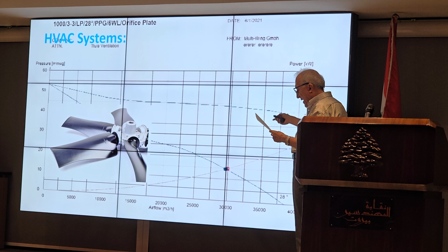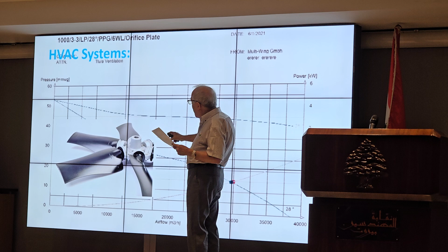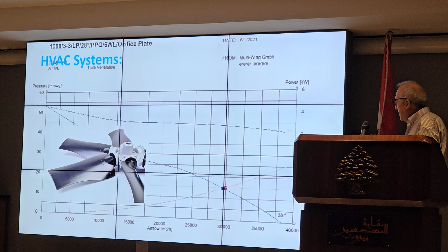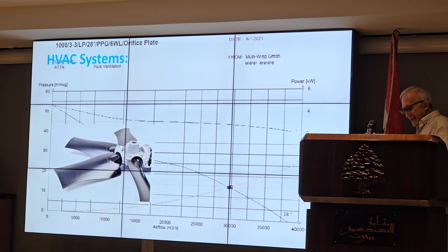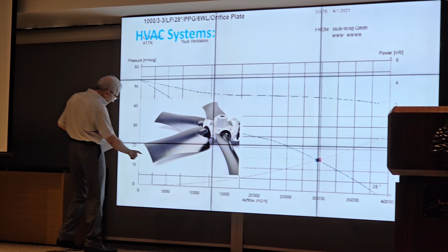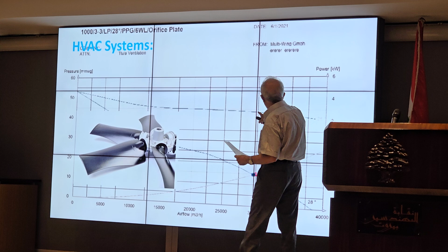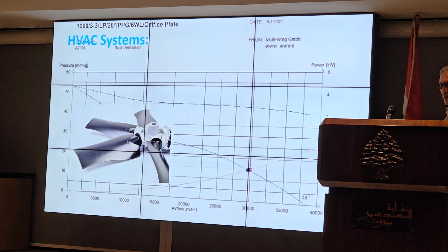Here for the fan that we have used, we use this highly efficient fan with adjustable pitch for optimum performance. We had recent supply challenges due to the drone industry demand for these fans. So now we have difficulties to get them in Lebanon because they may think that we are using them for drones. But because they are very efficient, we operate here at 30,000 and 150 Pascal, consuming almost 3 kilowatt, and we use 20 of them. The total was 60 kilowatt for this factory.